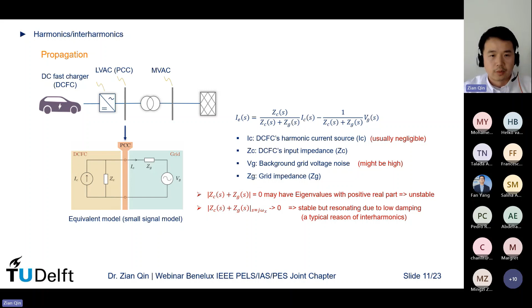Even if that's not the situation, the denominator may have a value which is close to 0, right, at a certain frequency. In that situation, even if the grid connection is stable, due to this very low value of the denominator, the harmonic emission and the background noise can be very much amplified at the PCC point, and eventually you will see harmonic issues that are beyond the limit. So to briefly summarize, if there is a harmonic or interharmonic issue, very likely it's because of the mismatch between the two impedances.